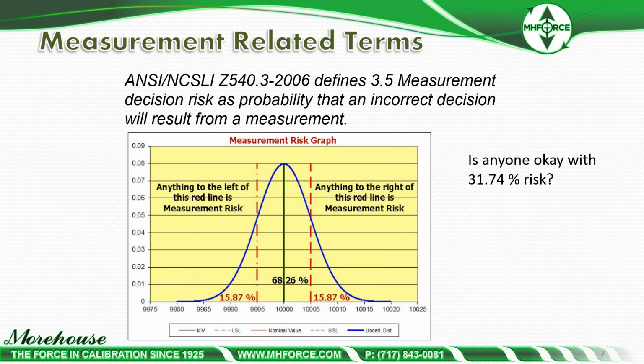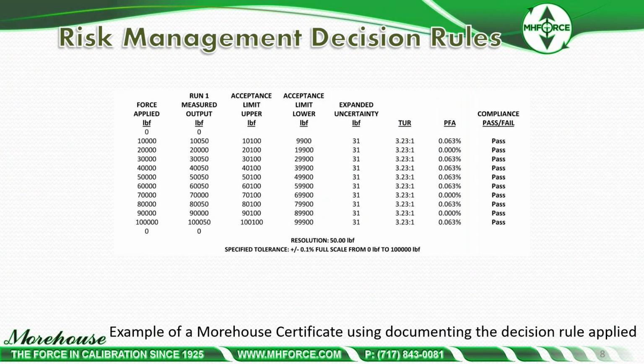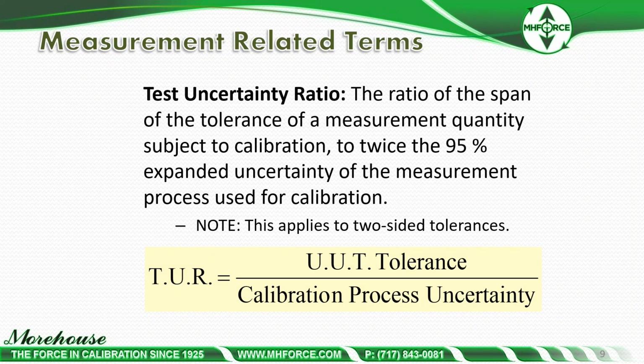31.74% chance of it being bad, and me saying it's good. So not too good on here. Here's just a simple thing. You can see you look at the PFA, that's probability of false accept. You look at your expanded uncertainty, and this one simply you subtract the measurement uncertainty from the value, and that's one of our certificates.